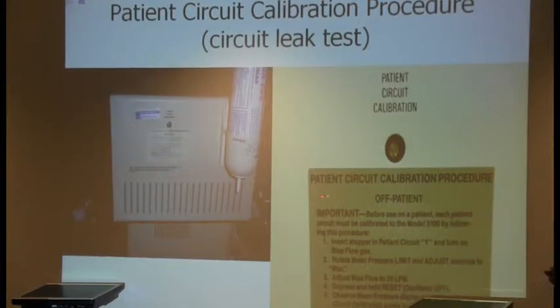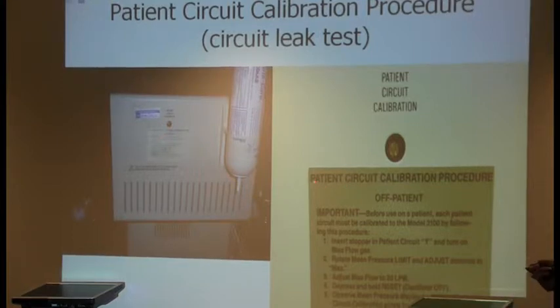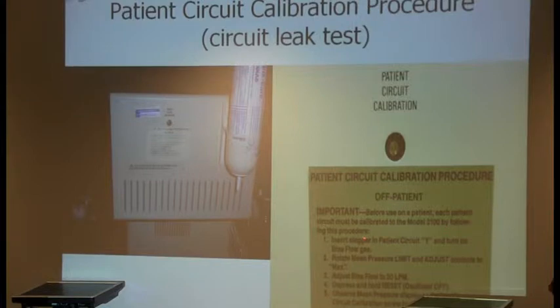So on the side of the machine, this one's rubbed out, but some of the machines have this. We have to get some new ones. It says: off patient. Before use on patient, each patient circuit must be calibrated to the model 3100 by the following procedure. So this is your calibration. This is not your EST.